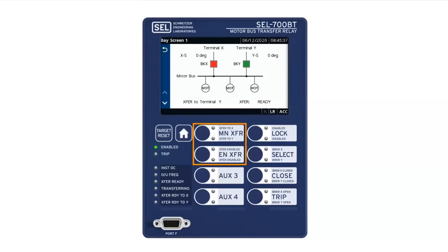Here's one question. Would you typically try fast transfer first, if that fails or is not applicable, in-phase transfer, and last, residual voltage? Yeah, that's the sequence. The relay will run all three algorithms at the same time, but the fast transfer, if possible, would always win. It would always be the first one, assuming that the voltage is healthy. If the voltage is not healthy from the fault that initiated the transfer, then fast is out of the question. You could also disable them one at a time. You can disable them independently if, for some reason, you don't want to try a fast transfer.